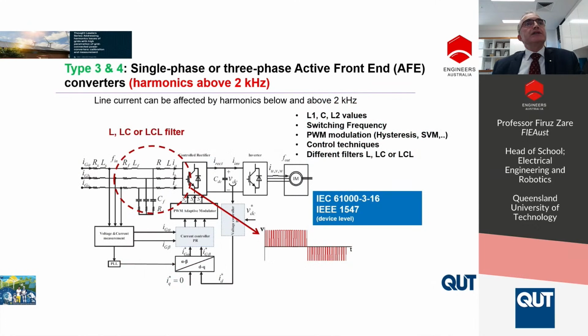So why is this technology so critical? This technology is so critical because there are many design factors which can be different from one product to another. For example, the LCL filter is significantly important for this design to make sure that the switching pattern and the voltage stress coming from that inverter can be mitigated at the grid side, to make sure that voltage stress is minimized as well as the current waveform being sinusoidal.